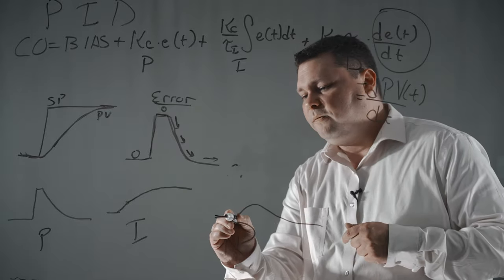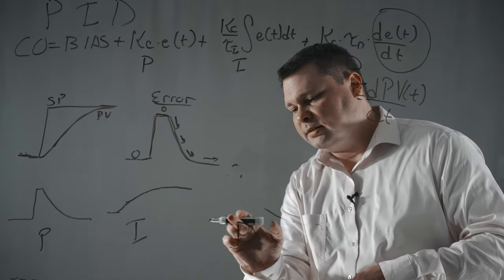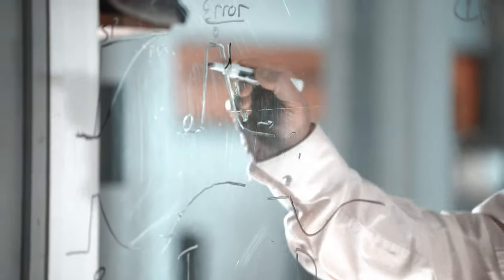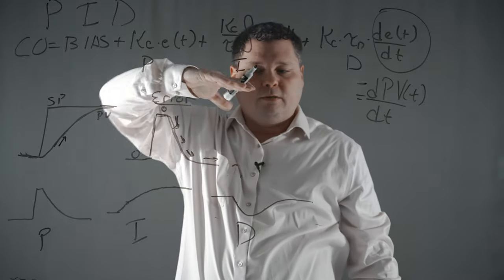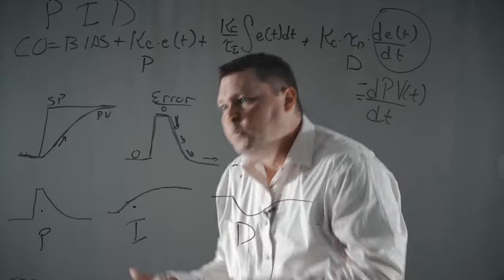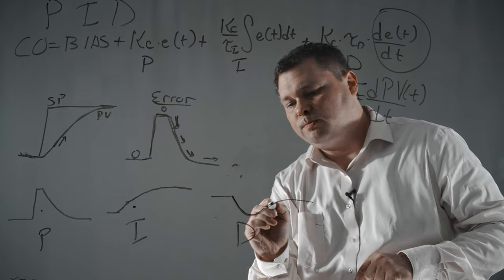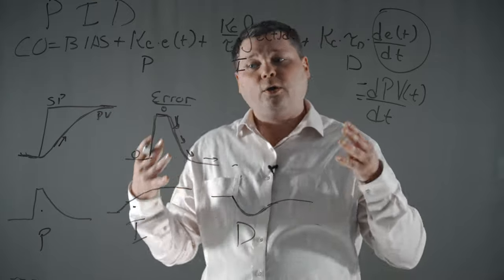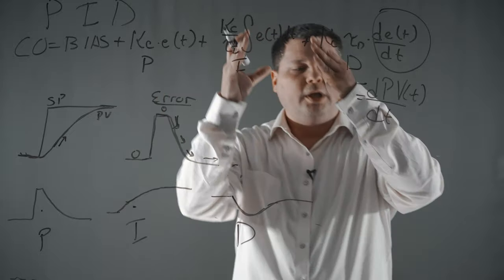What's interesting is the derivative doesn't actually work in the same direction as drawn — it actually does the exact opposite. It starts up, then goes down and comes back up again, because it doesn't like when the error is changing or when the measurement is changing. When the measurement is moving, the derivative wants to tamp that down. So the proportional and the integral are moving that process variable up towards the set point — they're driving, they're pushing — while the derivative is actually pulling back and saying, 'I don't want that measurement to be changing that quickly.' All three go together to create your proportional integral derivative.